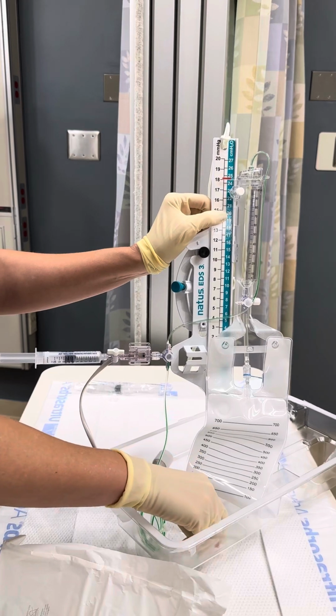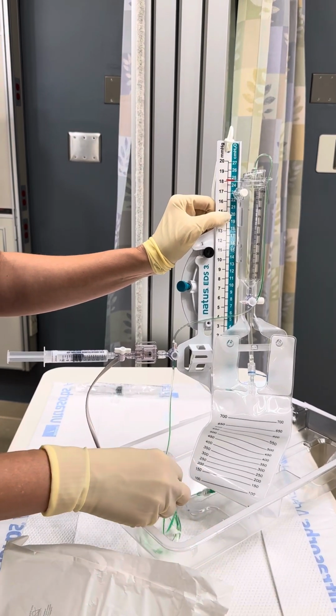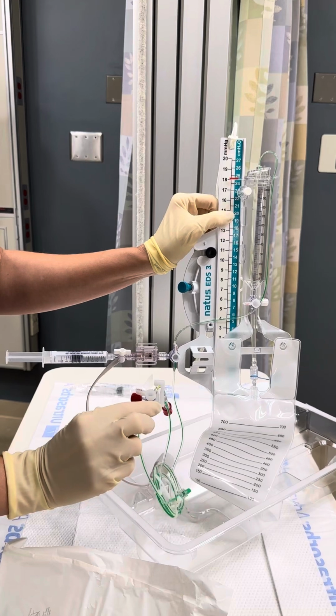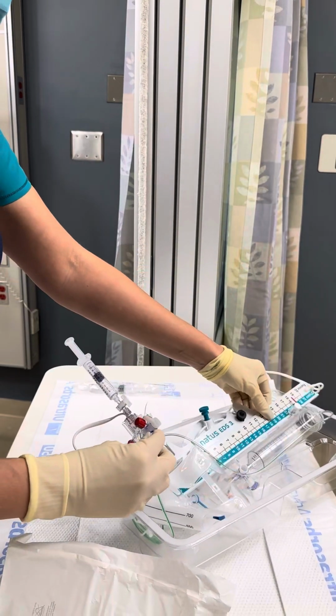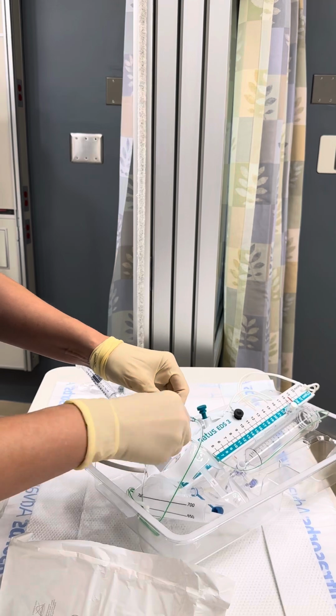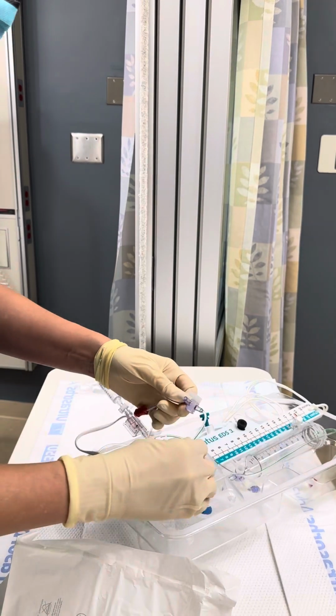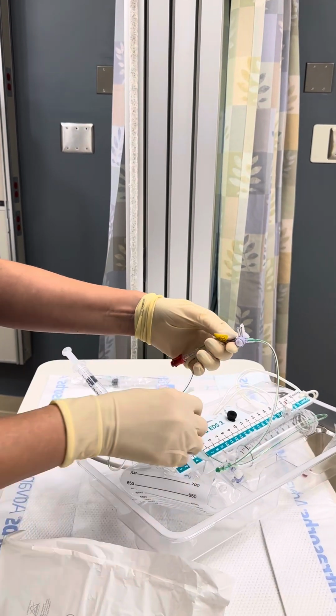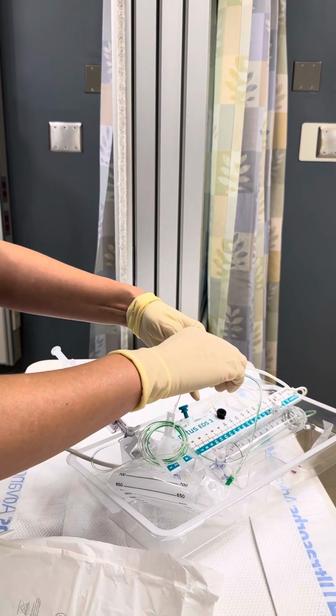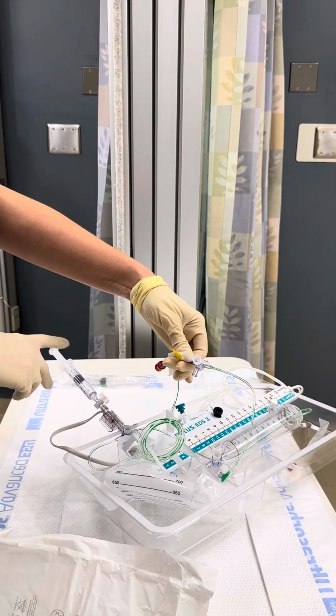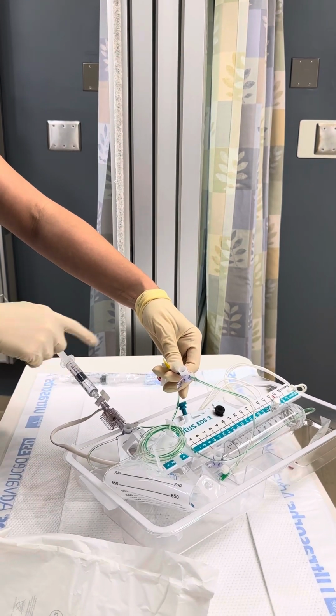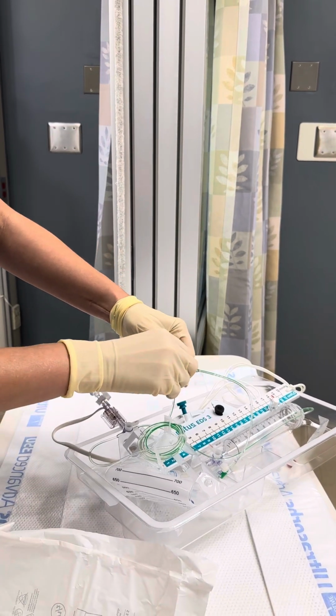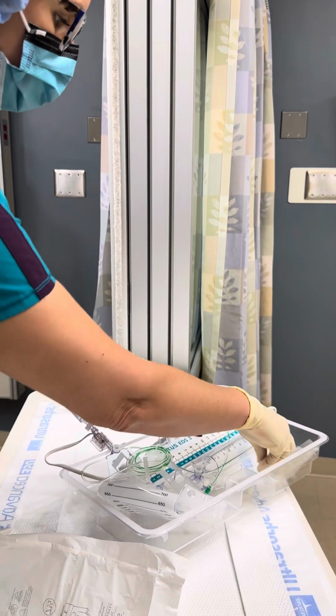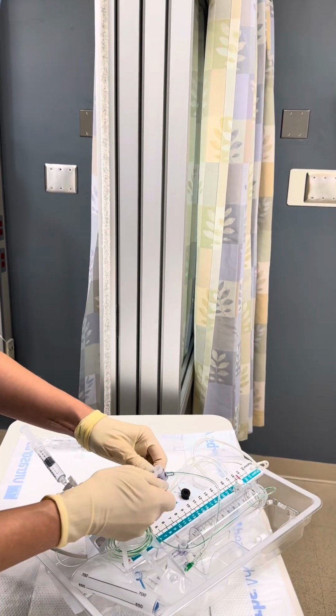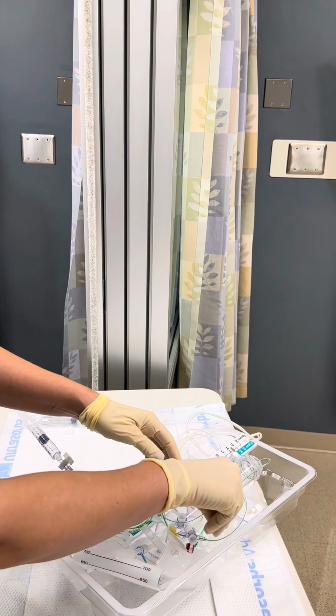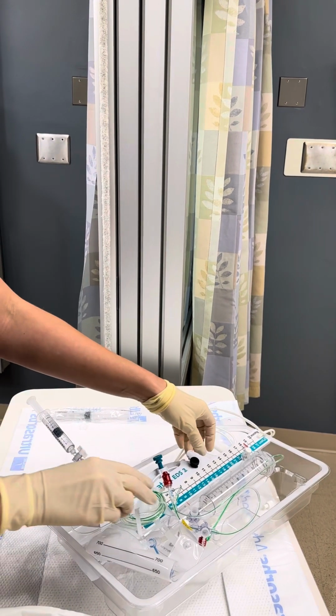Be sure to also prime both ports of the stopcock on the patient line. There's actually only one on this setup, so we're going to take this red cap off and set it aside. Then we're going to turn it off to the end of your patient line and then flush. There you go, got a little water in there. Now you can turn it back off and put your red cap back on. Turn the patient line stopcock off to the patient.